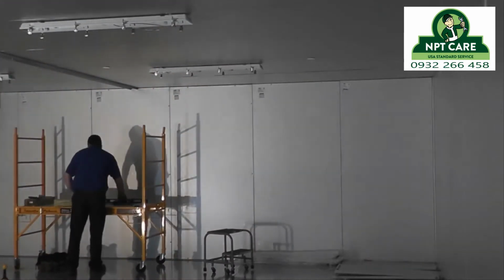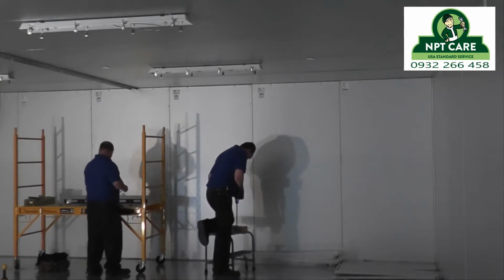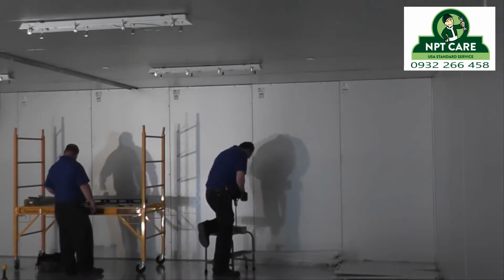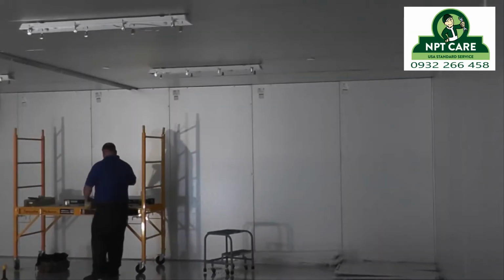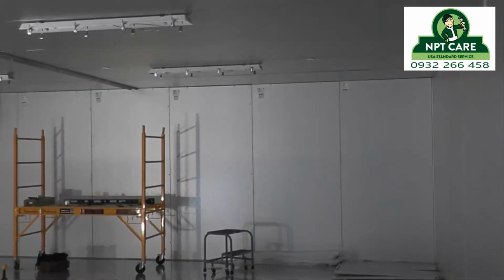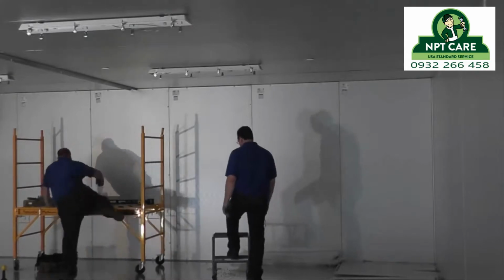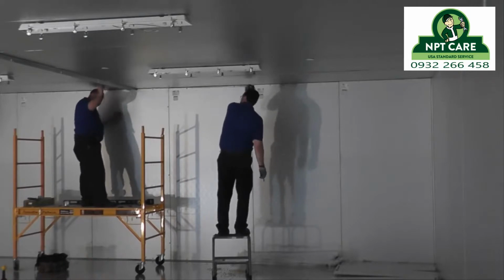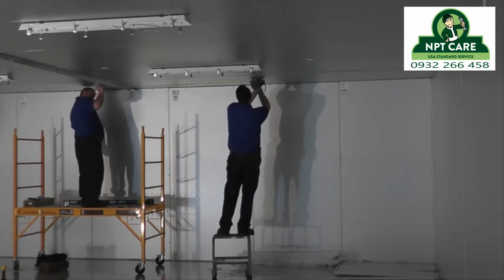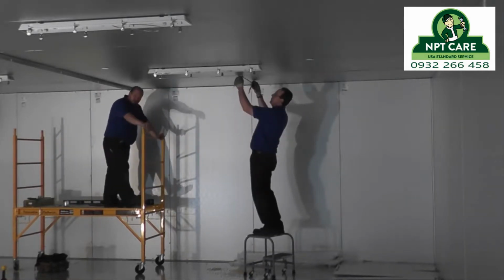One thing to note as you're watching this, you can see the lights on the ceiling. Those are actually LEDs, and there's 9 of them in here. And they're spaced perfectly, perfectly aligned. You'll see later on in one of the other videos that 3 of them have been oriented differently. The reason for that is after we put these up, the sprinkler guys came in and cut their holes in completely, and then said to our electricians that they had to move the lights because they were too close to the sprinkler heads for whatever reason. I don't know why, but that's why later on you might notice that those lights are kind of in a funky orientation.